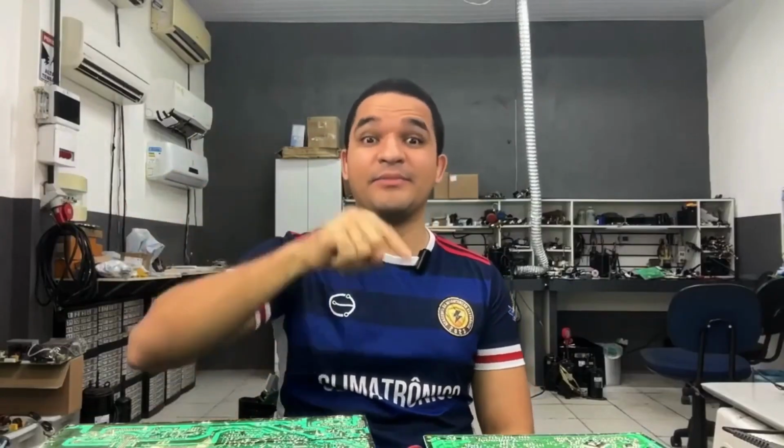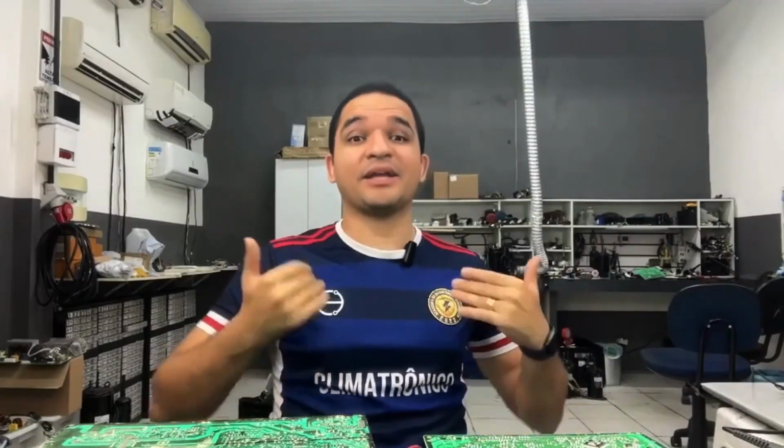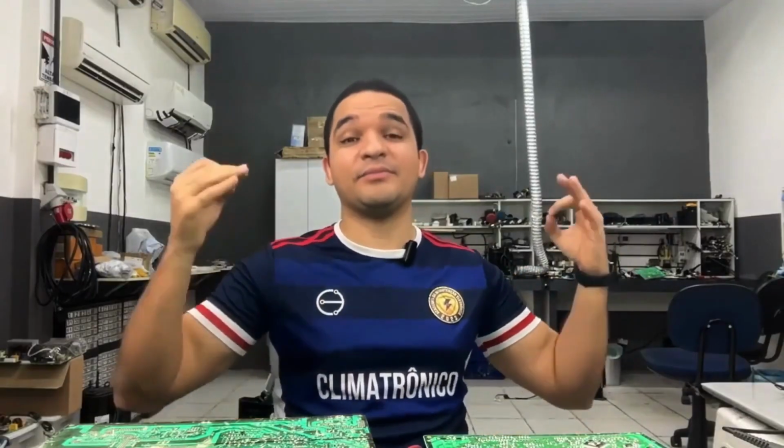So which voltage is this error referring to? The DC voltage of the power capacitor, the high DC voltage. Why? Because it is the only one that the board measures. The board measures both AC voltage and DC voltage. If it says it is a DC voltage error, and the only DC voltage that the board measures is the 310 DC voltage, then make sure to take notes.